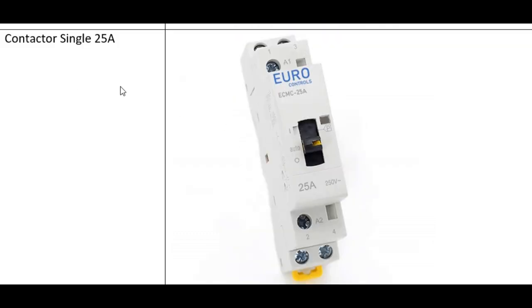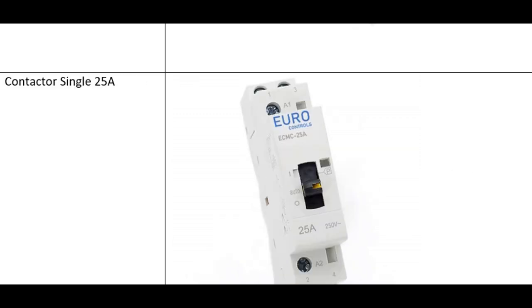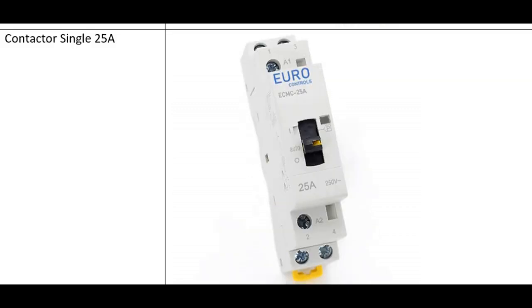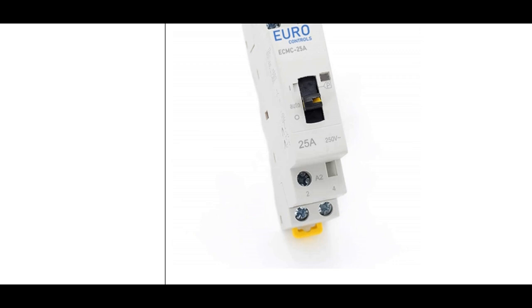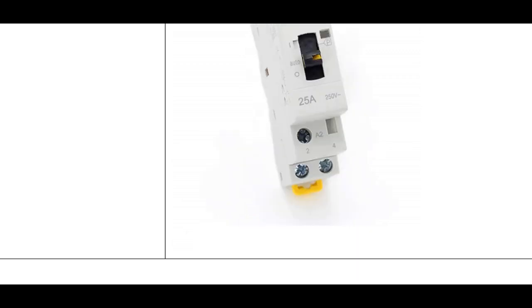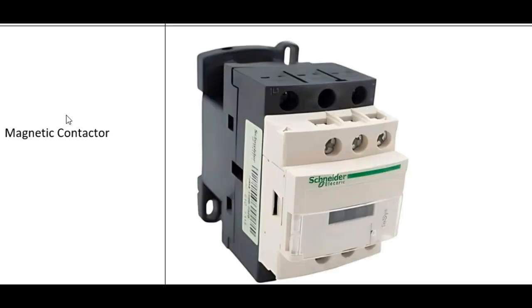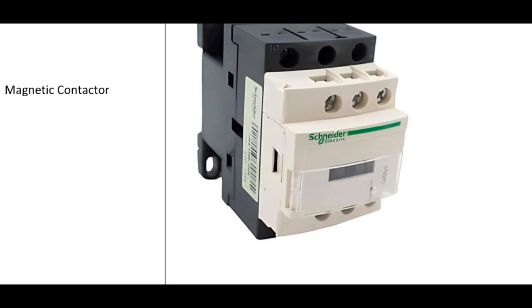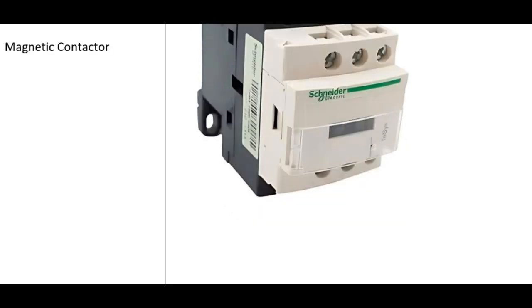Okay. Next we will see about a contactor. Single pole contactor, that is 25 ampere. Single pole contactors are commonly used in various appliances where only one phase needs to be controlled, such as in lighting systems, small motors, air conditioners, refrigerators, etc. This one is a magnetic contactor. A magnetic contactor is an electromechanical switch used in applications that require a circuit on or off process, such as starting motors, heaters and lighting applications.